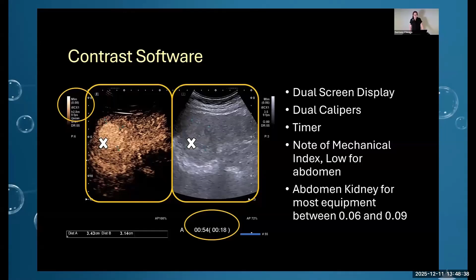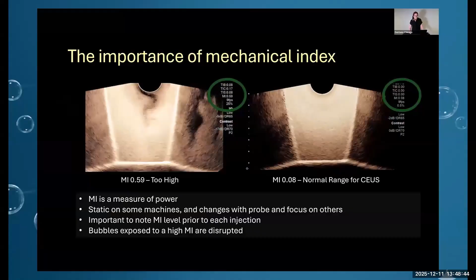And then you have to make note of mechanical index, which is usually quite low for the abdomen. We'll have a look at that. Abdomen and kidney scanning, you often use between 0.06 and 0.09 MI on most equipment. So this is the importance of mechanical index. We call these our contrast martinis.